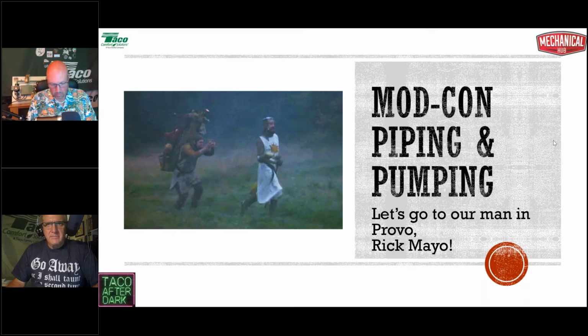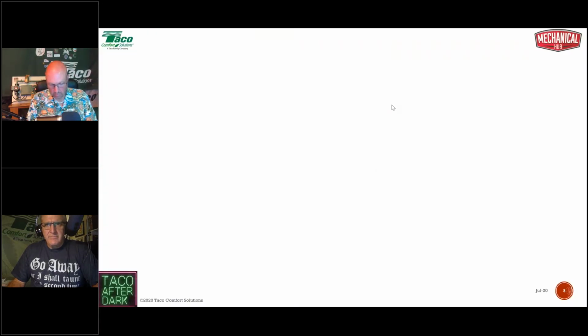Again, it could be better, but not everybody's doing the 0 to 10 with a small enough circulator that gives them what they need. And let me emphasize that. When I say small enough circulators, people that got pumps on their boilers, if you can't ever go with an ECM circulator, you can't ever go lower than low. And if low gives you a real tight delta T anyway, you can't do any better. So a lot of those boilers sit there at their lowest setting and they still have delta T's of 10 and 15 degrees. So it's kind of the same thing. Again, use it if you can. It's more important that I emphasize the fact that you size the pump right from the get-go and you'll be better off for the whole season.